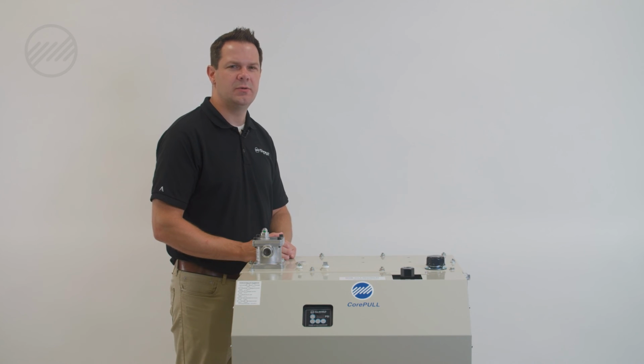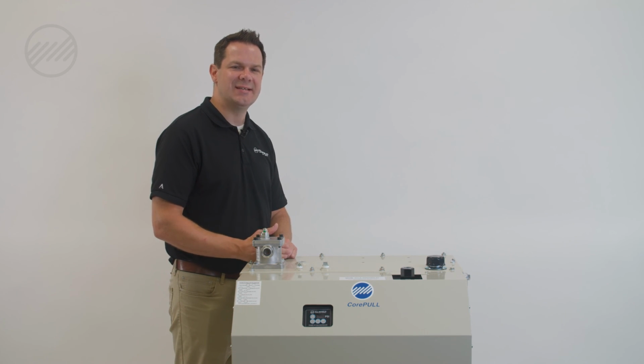Once an alarm code or error code has been generated and you've made adjustments to correct the situation, remember that most times you will need to cycle power to reset your alarm. Simply making an adjustment will not reset the alarm. Turn power off, wait for it to discharge 10 or 15 seconds, and then turn power back on to see if your alarm occurs.